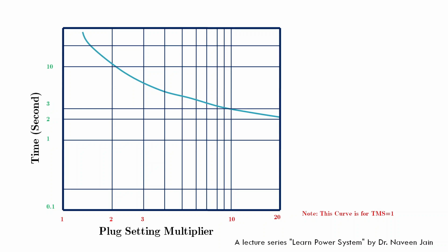In an induction relay, the pickup adjustment is by taps because the ampere turns at pickup are the same for every tap setting. Therefore, at a given multiple of pickup, the coil ampere turns, hence the torques, are the same regardless of the tap setting used. Further, it is important to notice here that the time multiplier setting is 1 for this curve.